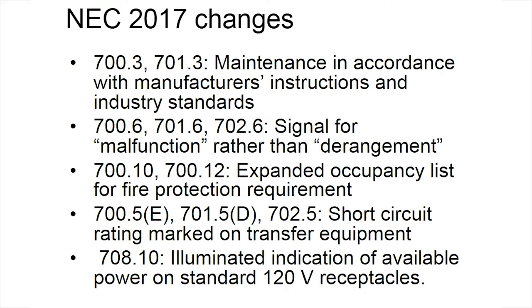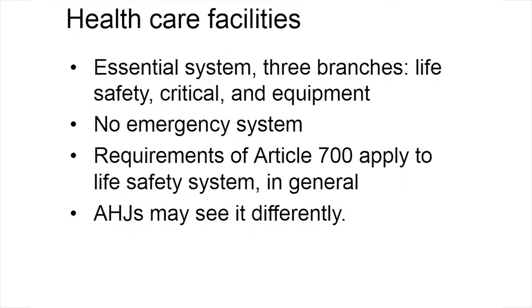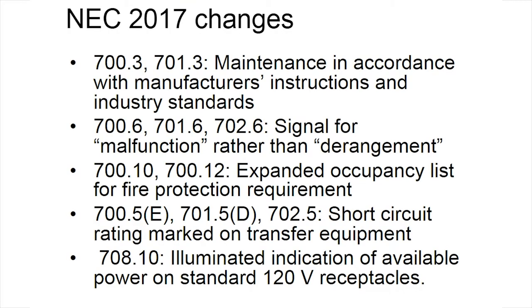And finally, we'll look at... let me back up one. So hospitals no longer have an emergency system. The life safety system generally falls under 700, except where 517 says something else. And it's worth noting that AHJs might take different views about whether the critical branch falls under Article 700 as well. The definition of an emergency system, things that serve functions whose loss could present a danger to human life, certainly applies to at least parts of the critical branch. So it's possible that an AHJ may declare the critical branch a de facto emergency system and try to enforce those requirements on it.